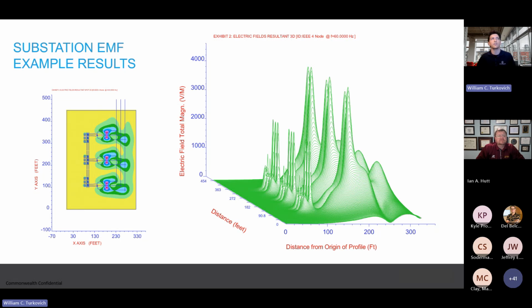Both these cases show the electric field generated by the equipment itself. You can see that tall peak is the transformer, because the voltage is highest there, directly affecting the electric field. You can see the lines getting closer together the higher the peak is. There's another spike where the breakers are, with conductors getting close together despite their typical separation distances. You can also see where the high voltage lines come together, creating a couple of hot spots.